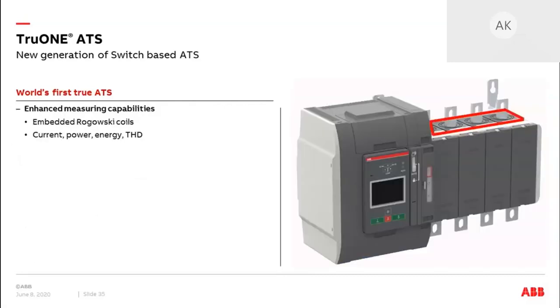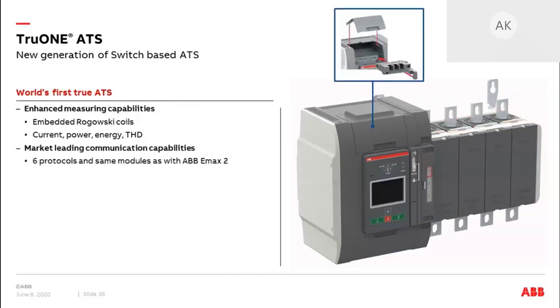TruONE ATS has embedded Rogowski coils, which means it can measure current, power, energy, and total harmonic distortion — all without any external current transformers and wiring, everything is already inside the unit. TruONE also has market-leading communication capabilities with six different communication protocols. And since it shares the same software environment with ABB Emax 2, the same communication modules are used on both devices, making it a uniform platform that's easier to adopt when you already know one of these products.